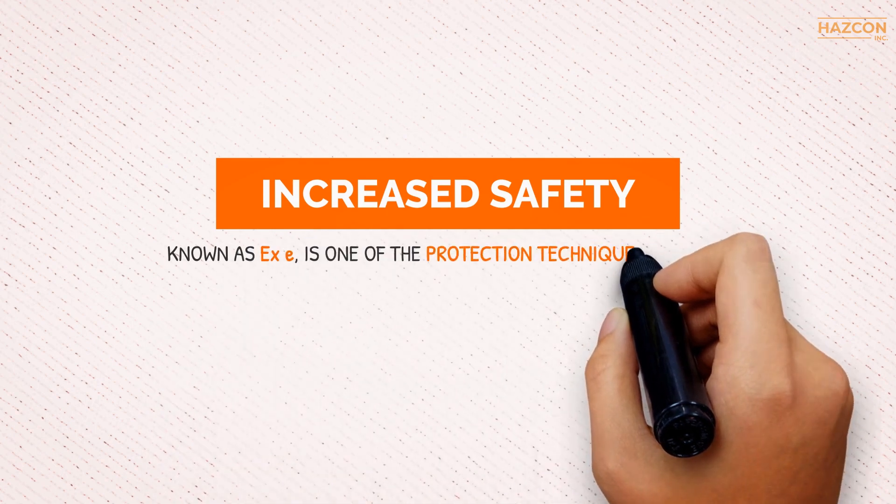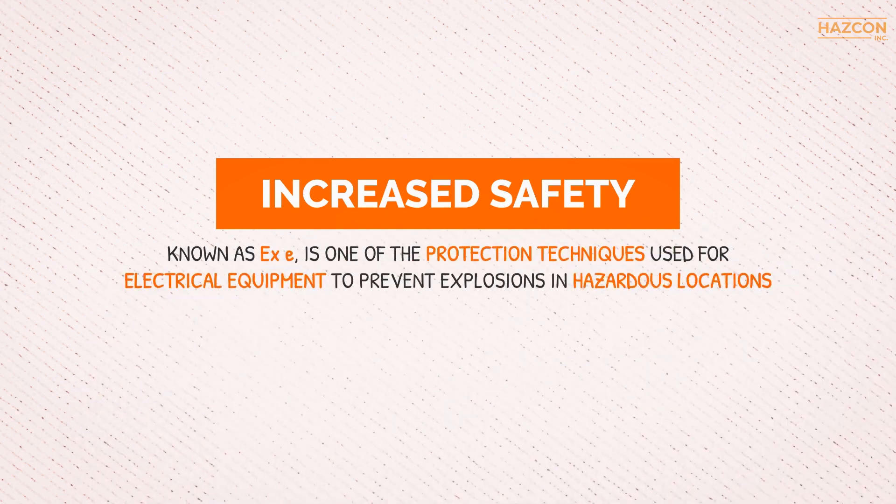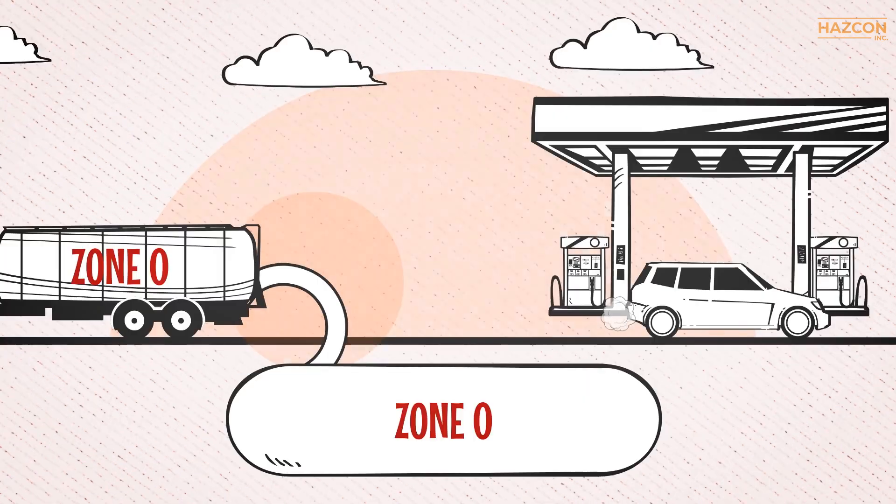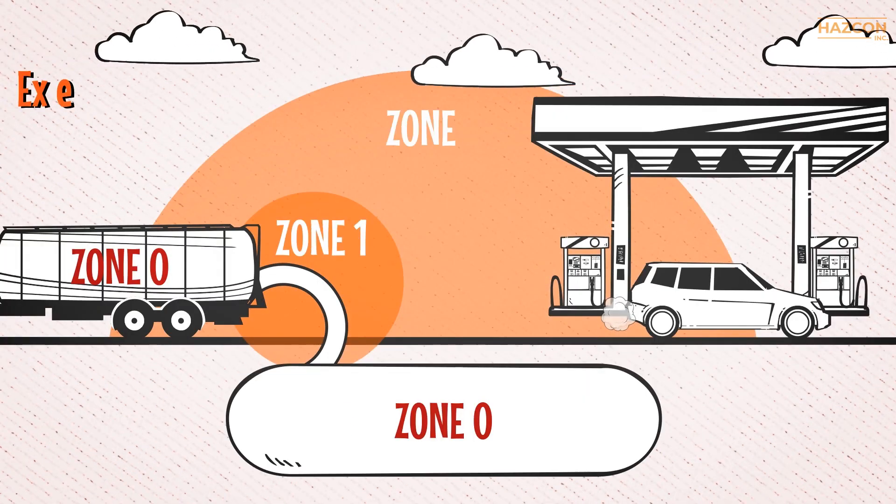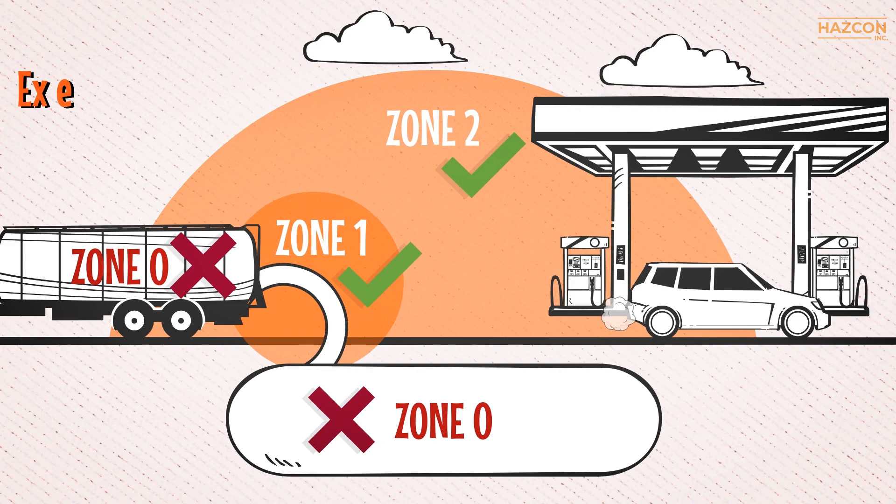Increased safety, known as Ex e, is one of the protection techniques used for electrical equipment to prevent explosions in hazardous locations. This protection concept may only be used in hazardous locations that are Zone 1 and Zone 2.